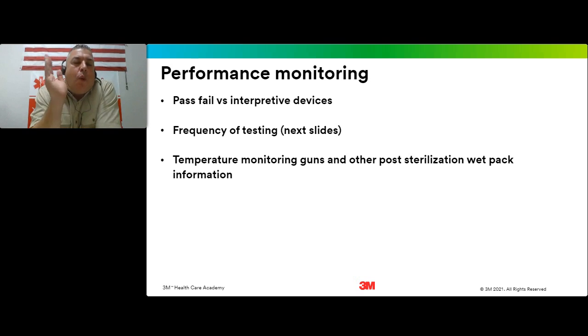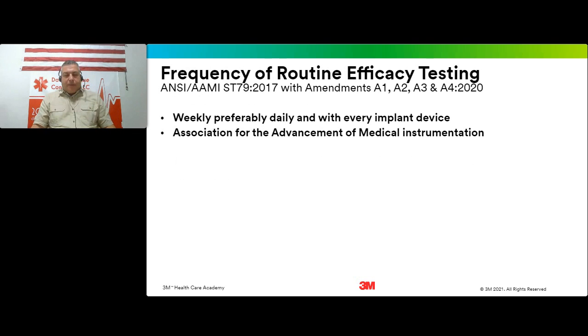But the point is, if you put a warm package on a cool shelf, you're going to wick the moisture out of the room. You're going to create condensate or water or wetness inside of the packs. A lot of times there are instances where the moisture could be created in chamber because you're having a steam issue, but more often than not, there's problems with post-sterilization.